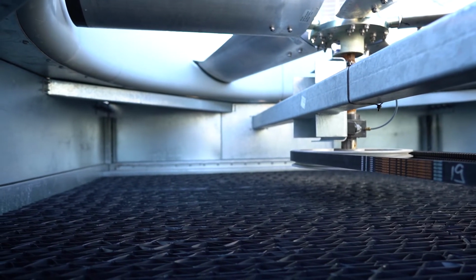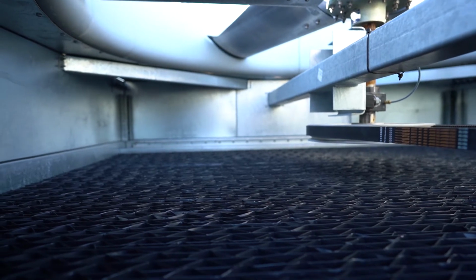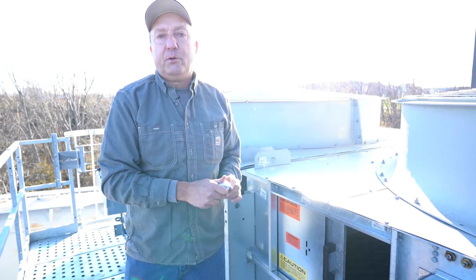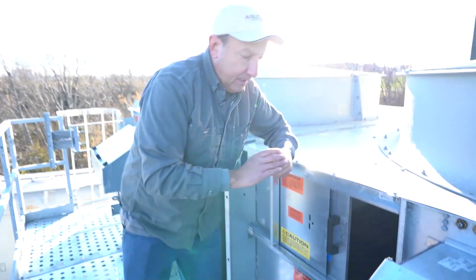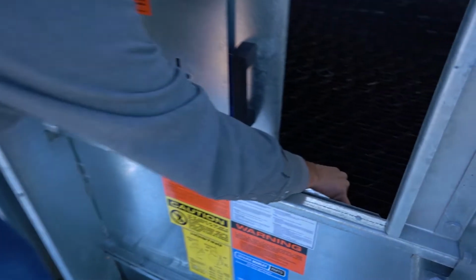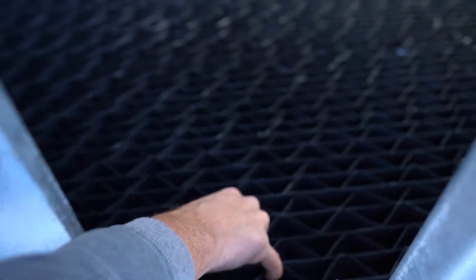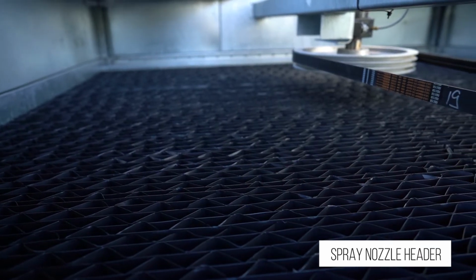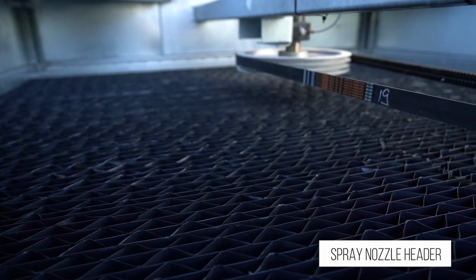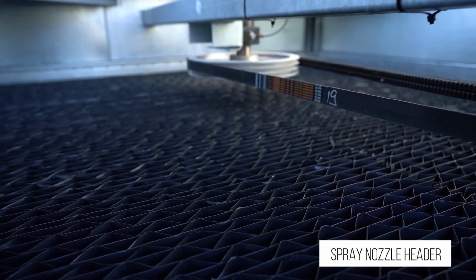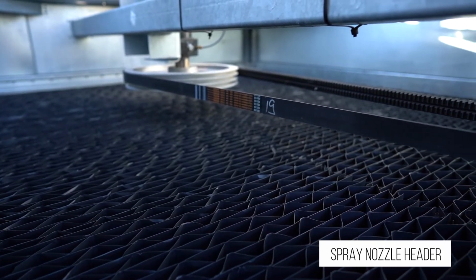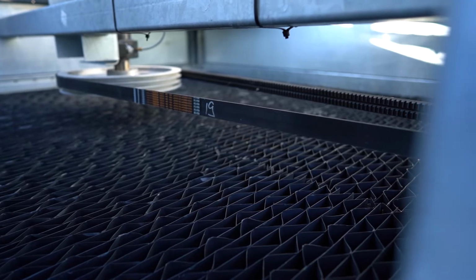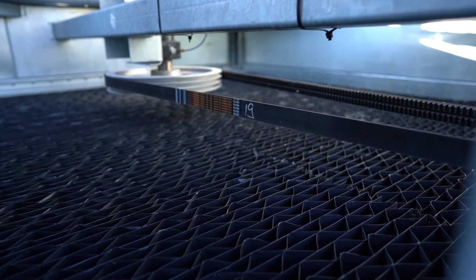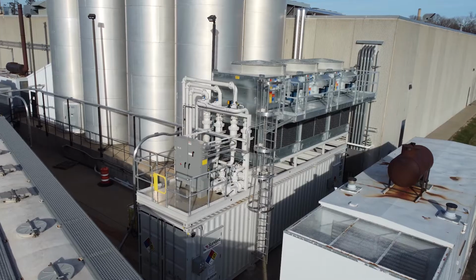Okay, one thing I want to point out is you can't see it, or it's not accessible from here without pulling the filter media. But inside here, if we were to lift this filter media, underneath here is a spray nozzle header. I believe it's 3-inch diameter, and there's a series of spray nozzles which spray the water equally around the tower system, and the fan draws the air across and cools the water to then in return cool the water circulating through our refrigerant condenser.